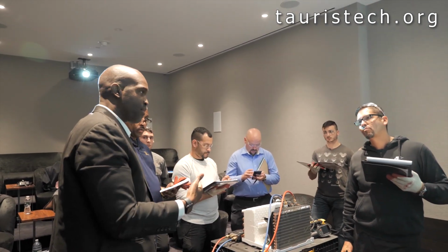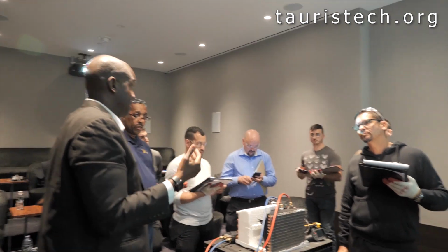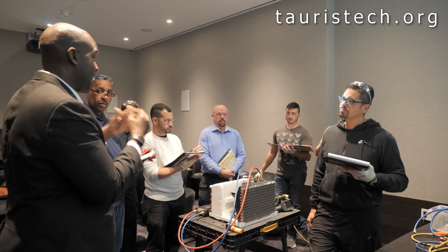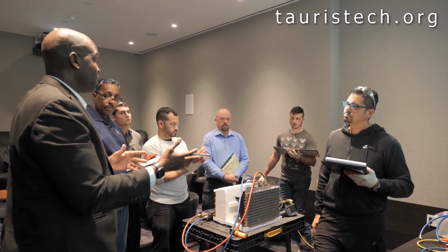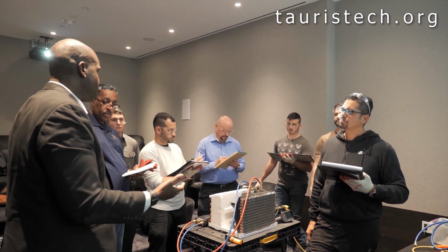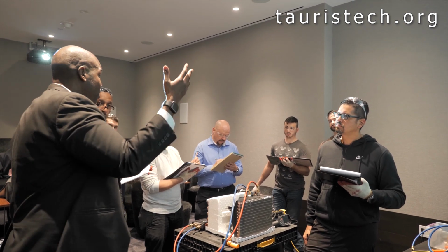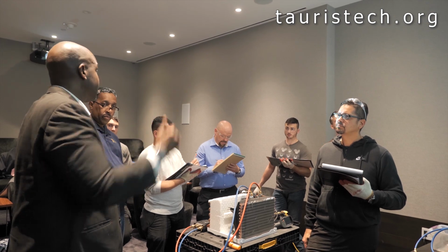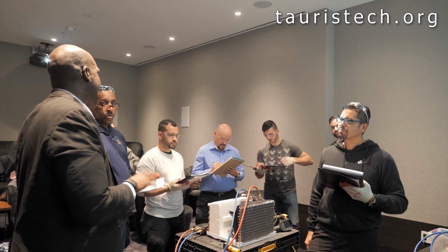Can we compress liquid? No, we cannot. So what's going to happen to my compressor? It's going to break. If it is superheated and above the saturation point, I know that it is vapor. You can't superheat liquid, right? So think about this. Water boils at 212 at atmospheric pressure. If I have water on a stove and it becomes steam and it becomes 220 degree steam, is there any liquid left in the steam? No. It is superheated. The problem that people have is they confuse superheated with hot.